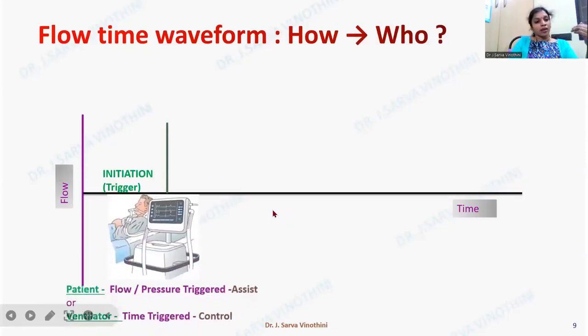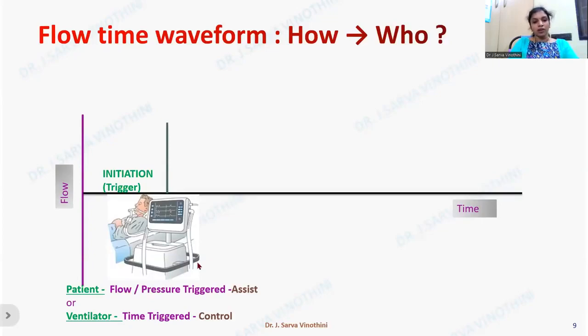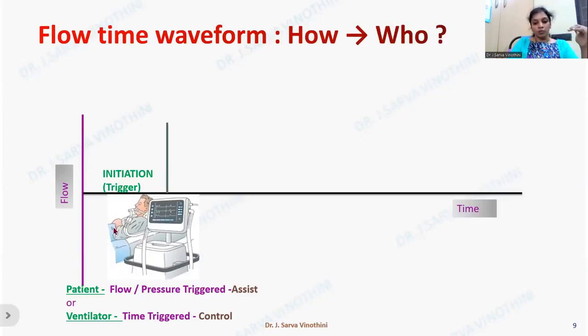Now that we know how the flow-time scalar is plotted, let us see who does all these things — who triggers the breath. The trigger could either be by the patient or by the ventilator. If triggered by the patient, we call it an assisted breath; if by the ventilator, a controlled breath. In a controlled breath, the trigger is always time — for example, 10 breaths per minute means the ventilator gives a breath every six seconds. If the trigger is flow or pressure, it is an assisted breath where the patient initiates flow or negative pressure, after which the ventilator initiates the flow.